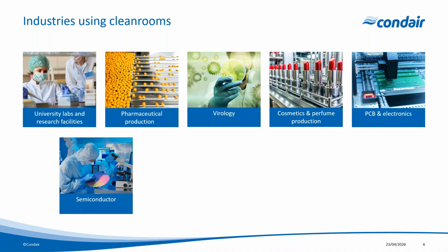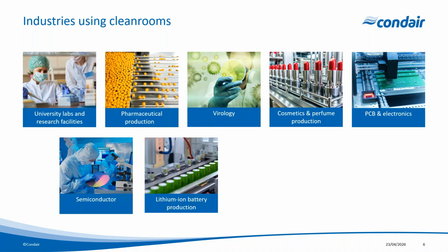It's a very similar story with semiconductors. We don't want static discharge interfering with or damaging a semiconductor. So it's critical to be over the static threshold. Lithium battery production is a good example of where we want low relative humidity because we have the potential for a reaction with moisture and lithium. And this can be explosive. So generally, moisture content in these applications has to be ultra low at around 3%.